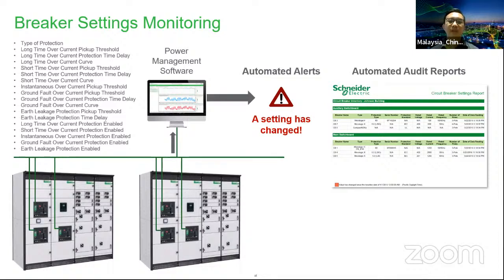This is why we always advise connecting the OCR or protection relay back to your power monitoring system, or at the very least, start using breakers with an integrated trip unit. Because with breakers incorporating a trip unit, the whole breaker can be connected back to your PMS system, and from there you can not only measure and reset settings according to current usage and protection needs, but also track the health of the breaker itself.